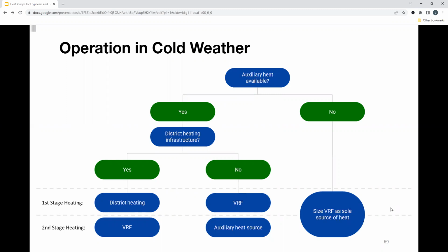But if you are in a retrofit and you do want to keep your steam heat or anything of that nature, maybe it's district heating. What do you have? If you don't have it, then use VRF, and you can use VRF as the first stage, right? And auxiliary heat is the second stage. Or if you do have district heating, and you want that to be the primary heating in this instance, you can use district heating as the first stage and then VRF as the second stage. And I'm going to quickly tell you what to use in those two scenarios.